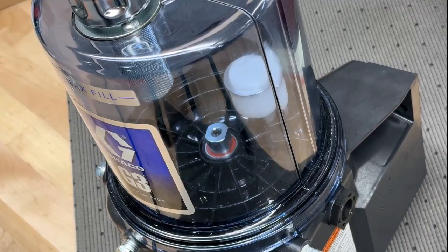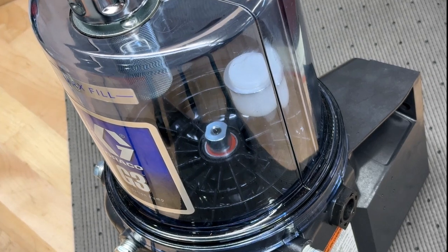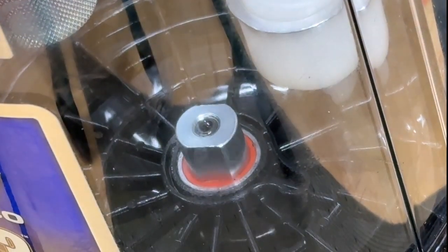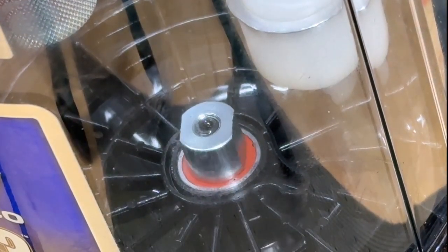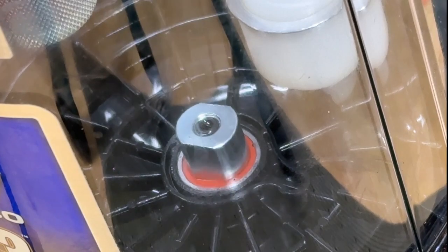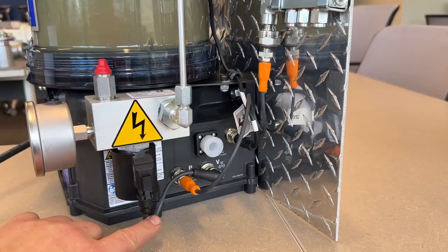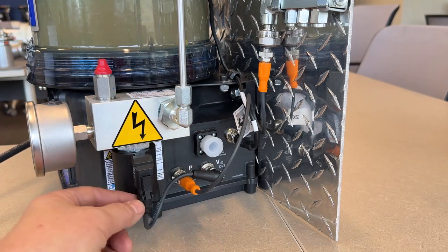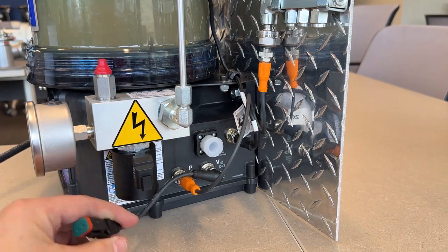An oil system doesn't have a wiper arm, so it can be more difficult to confirm the movement, but if you look inside the reservoir, there is a round nut at the bottom with 2 flat sides. You might be able to see this nut moving as long as your oil is not too dark. If pressure is not building while the pump is running, check the vent valve power cable. Be sure it is connected at both ends and that it is not damaged.